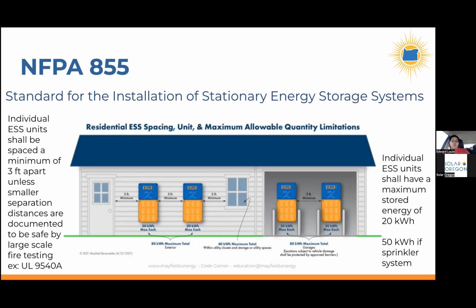And if you were to put it inside the home in a utility closet, a storage area, or a utility space, you're allowed up to 40 kilowatt hours. But if you were to put it in a garage, you can have up to 80 kilowatt hours. And if you were to put it outside, you were allowed up to 80 kilowatt hours.